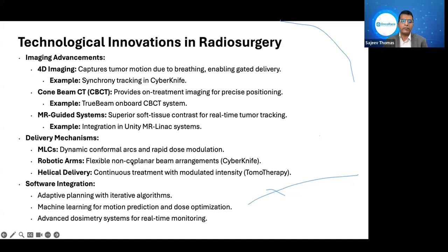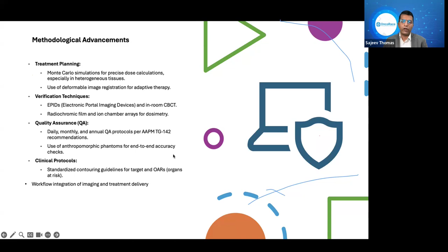If you look more into the methodological advancements, there is treatment planning using Monte Carlo simulations, which is available in CyberKnife, and also deformable image registration for adaptive therapy, and verification techniques using EPID, CBCT, radiochromic film, and ion chambers. Quality assurance includes daily, monthly, and annual QA protocols, anthropomorphic phantoms, and accuracy checks. AI-based contouring, online adaptations, and workflow integrations are also available with the new advanced features.